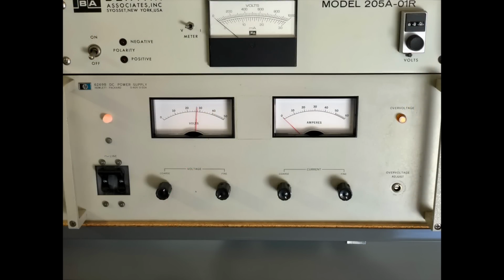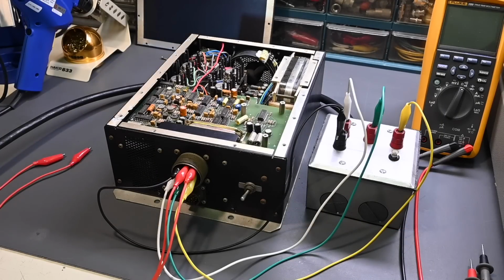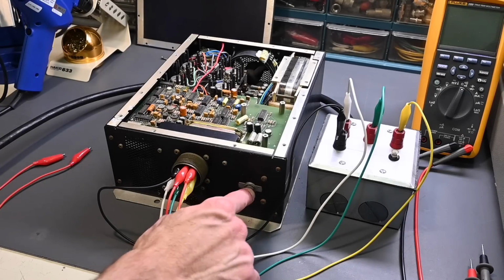The Unitron inverter likes to have about 27.5 volts, that's its rated input, and there's a little bit of loss in the wiring and connections between the DC power supply and the inverter. So I always run it at 28 volts to allow for that slight loss. Alright, this is turned off here, so that's good.